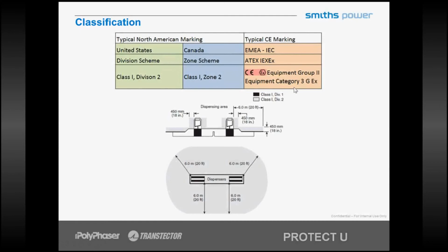It's very easy to put it all into perspective by considering our day-to-day gas pump. You drive in to get petroleum and you have a gas pump. When you're within a radius of 20 feet of that pump, you are in that region of space where the materials and the equipment all have to be marked for hazardous location. So all of the meters and the radios and the other electrical devices that are on or around those pumps are marked for this application.